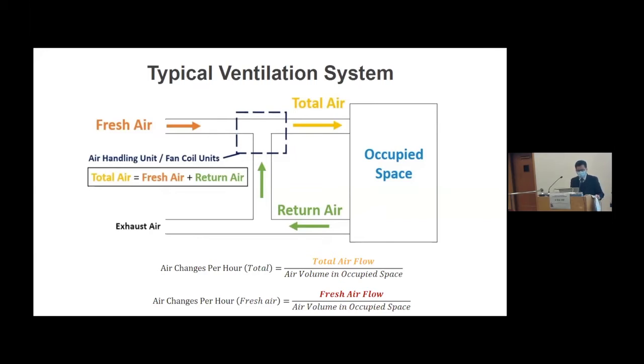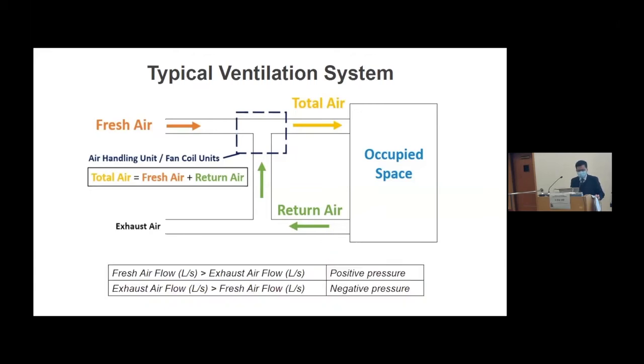While we are at this slide, I would also like to bring up a very simple concept about positive and negative pressure environments. To achieve a negative pressure in an occupied space, the exhaust air fan should be designed and operated to have a ventilation flow rate greater than that of the fresh air intake. And for positive pressure, it is just the vice versa.